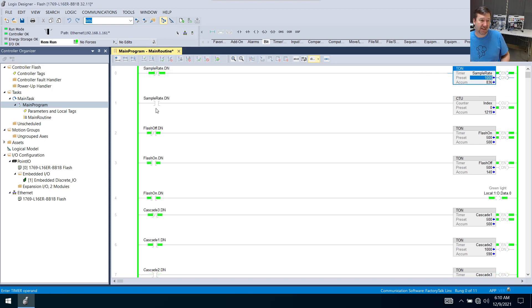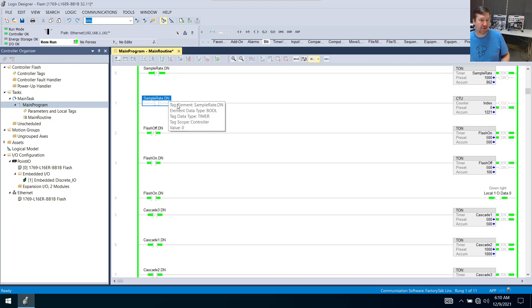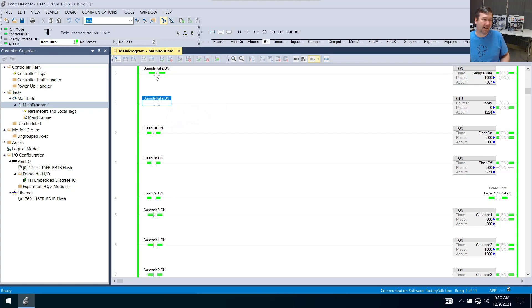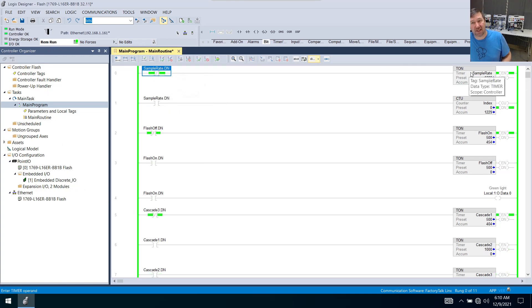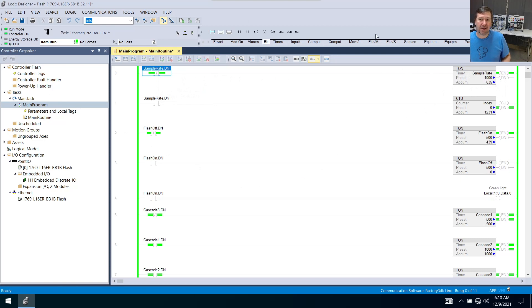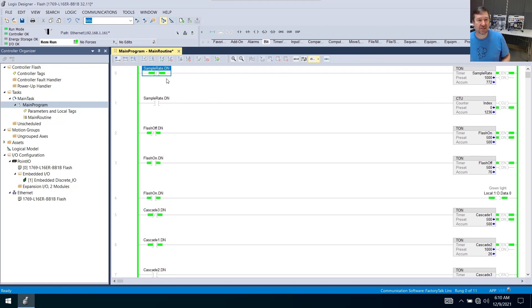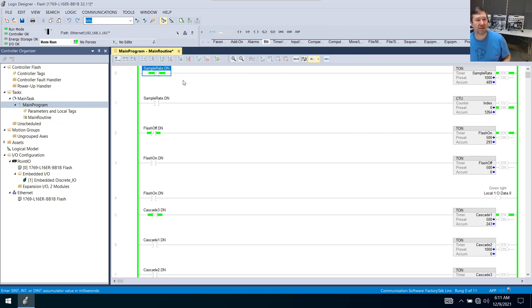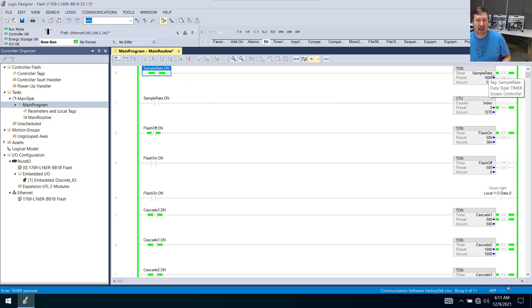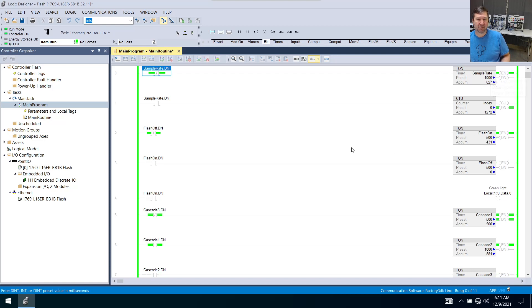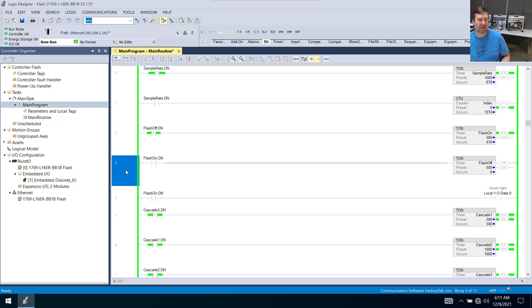And then it's going to come here, this is going to be a zero now. And it comes around next time. And this is going to look for a zero. It has one, it's going to be true again. So every 1000 milliseconds, this done bit is going to be true for one single scan, and then it's going to start over. Now as long as we keep this TON here from becoming false, we can do other things after that sample rate is done. And that's what we're doing with the flash on flash off here.